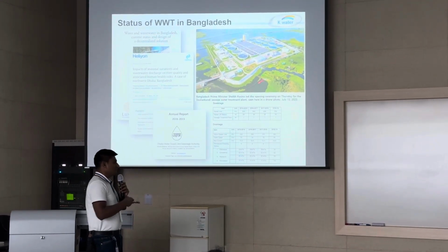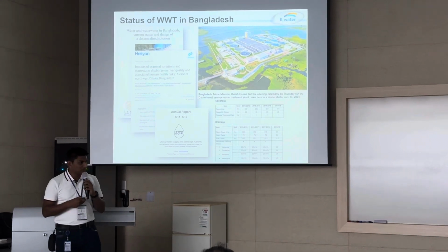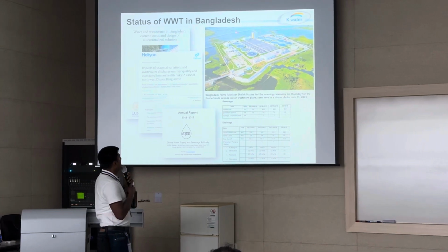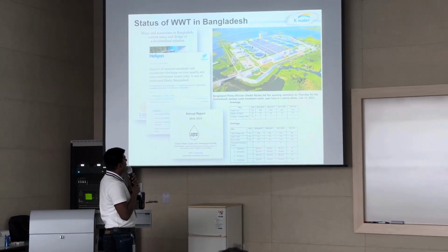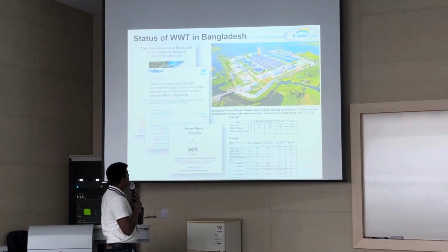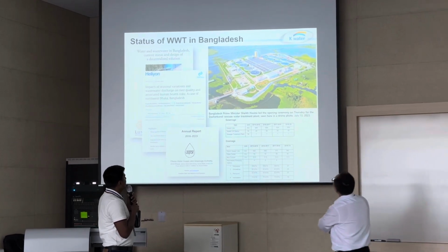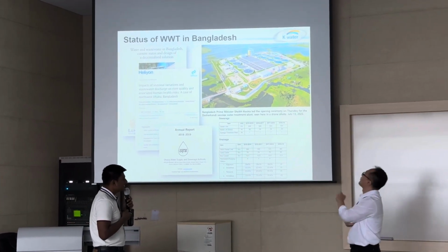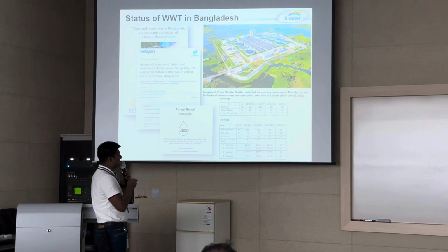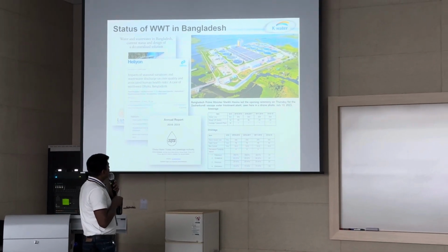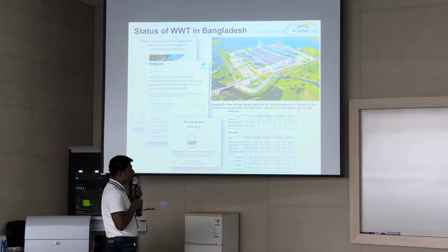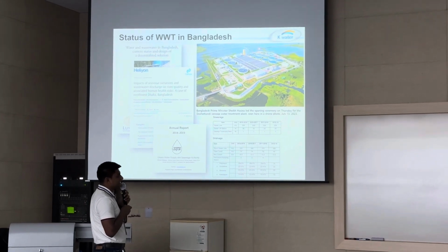We first reduce the moisture. The sludge we get has a moisture of 99%. Then we reduce it to 78%. Then we incinerate, and you can see there is an emission. This is the incineration building where we incinerate. It's a very complicated, intricate structure, and before we emit anything into the atmosphere, there is a flue gas purification unit on the back side of this building. That is why we cannot see it.